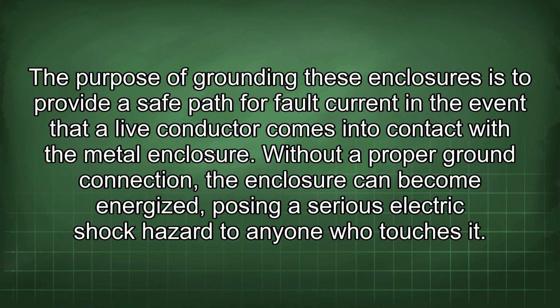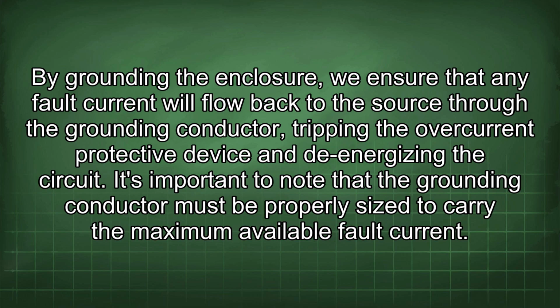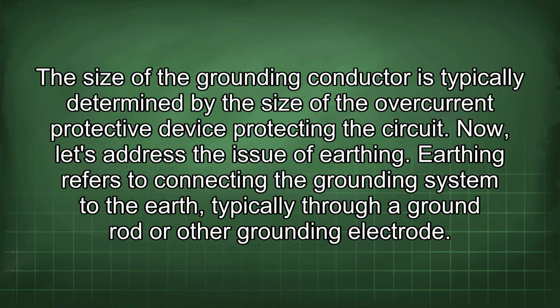The purpose of grounding these enclosures is to provide a safe path for fault current in the event that a live conductor comes into contact with the metal enclosure. Without the proper ground connection, the enclosure can become energized, posing a serious electric shock hazard to anyone who touches it. By grounding the enclosure, we ensure that any fault current will flow back to the source through the grounding conductor, tripping the overcurrent protective device and de-energizing the circuit. It's important to note that the grounding conductor must be properly sized to carry the maximum available fault current. The size of the grounding conductor is typically determined by the size of the overcurrent protective device protecting the circuit.